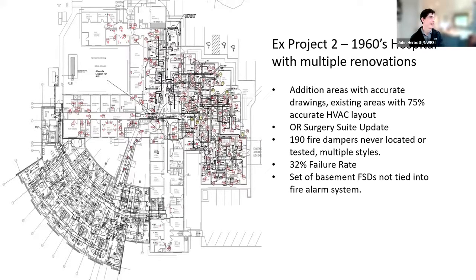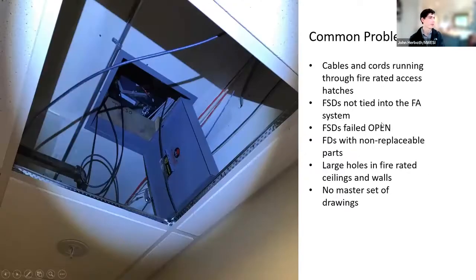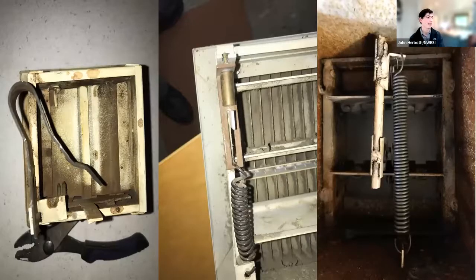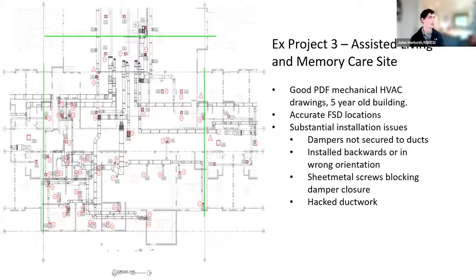All right, Larry was right. Hospitals we've gone through, high failure rates, non-connected stuff. This project definitely hand-holding the whole time with the client. You run into cables through fire smoke dampers, fire rated stuff staying open because of cables, all sorts of fun stuff. Then you run into dampers you've never seen before, Larry's never seen before, components you can't replace. Try to clean them up, put them back in. You have places where people are like, why is a damper here? And until you get all this tested and know where everything is and what type it is, you can't get rid of it. So, try not to be destructive with your testing, and note that you don't want to destroy it, but you've operated it and it seems functional. So do what you can to not destroy stuff, but you're going to have to replace some stuff.